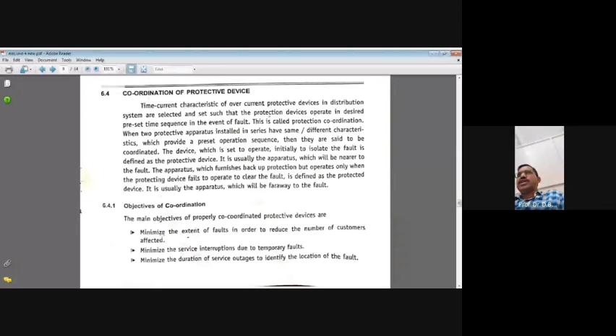We need coordination between the protective devices: lower rating fuse near to the load and higher rating away from the load. Here we have fuse to fuse coordination, circuit breaker to circuit breaker coordination, fuse to circuit breaker coordination, and multiple combinations of coordination. Okay, the main objectives of coordination.